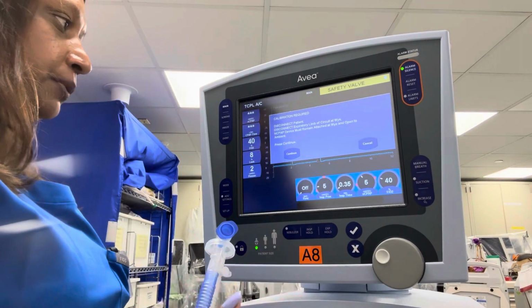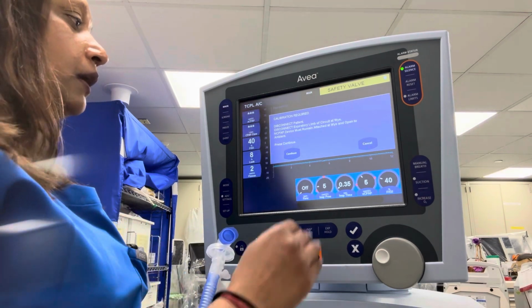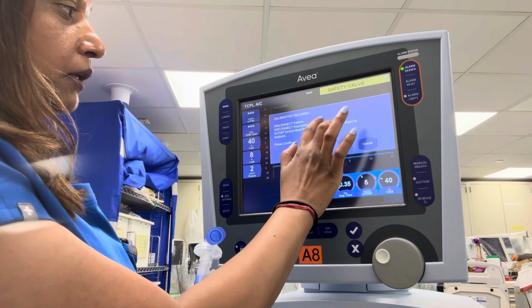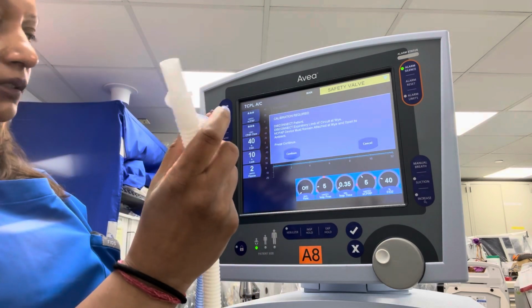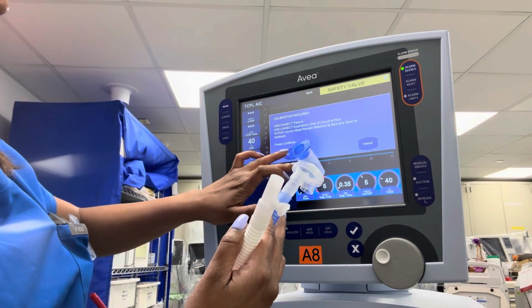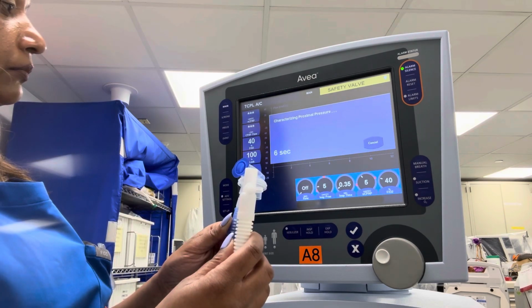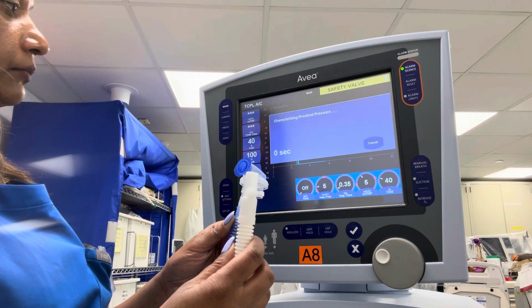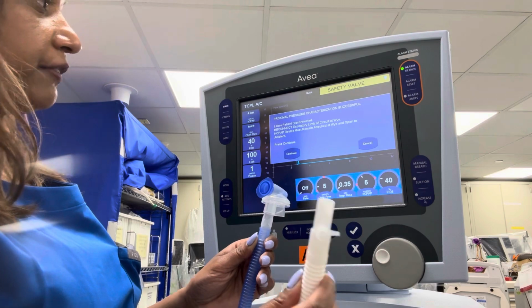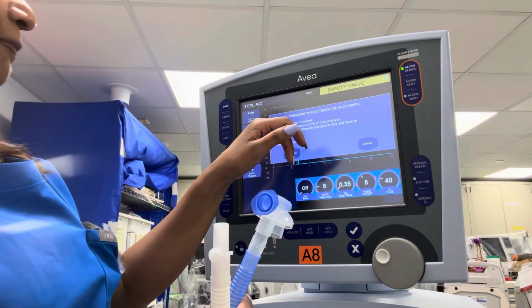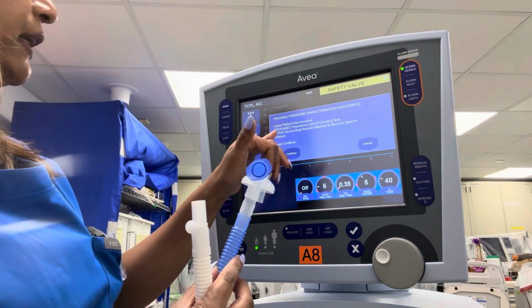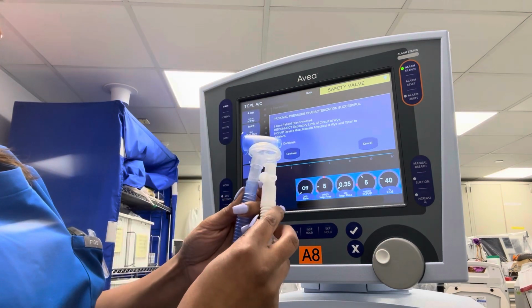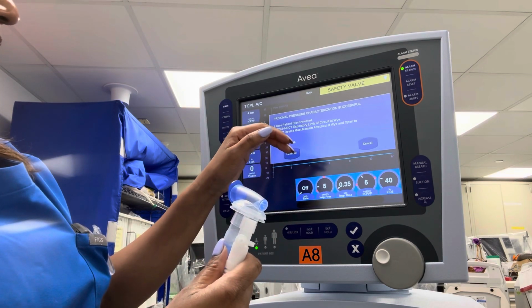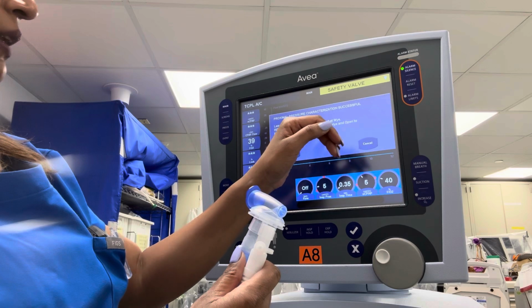It says to disconnect the patient. Like I said, there's no patient here. It says disconnect expiratory limb of circuit at Y. So this is your expiratory limb. So you will disconnect your expiratory limb, and then you are going to click continue. Perfect. Now it says leave patient disconnect, right? No patient. Reconnect the expiratory limb. So I will reconnect the expiratory limb. And then it says nasal CPAP device must remain attached to the Y.